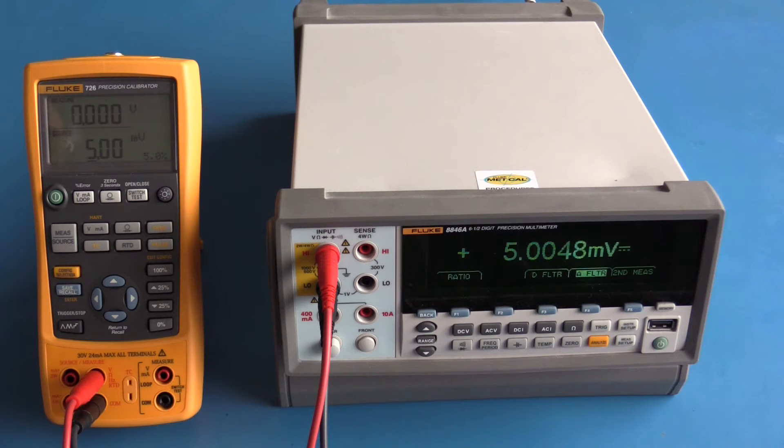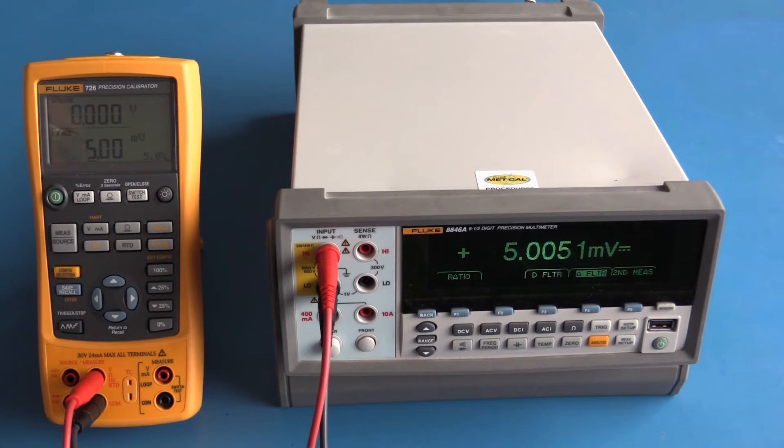I have the Fluke 726 setup to source five millivolts and the bench multimeter is showing that five millivolts. The setup I have for making this measurement is five and a half digits with an integration time of one PLC. I can change that.